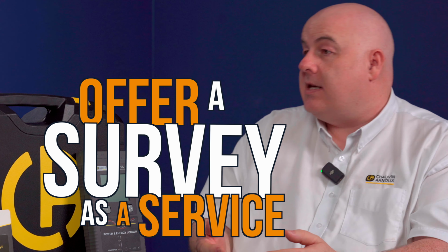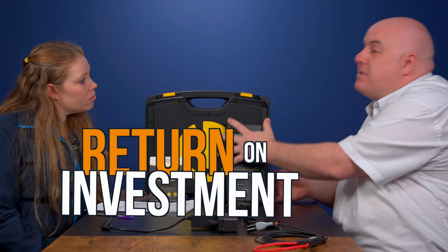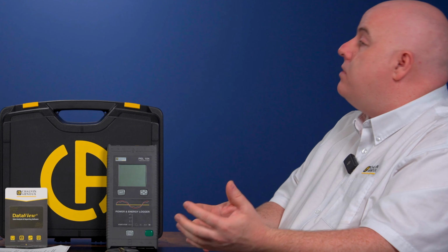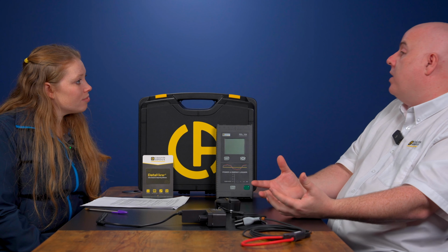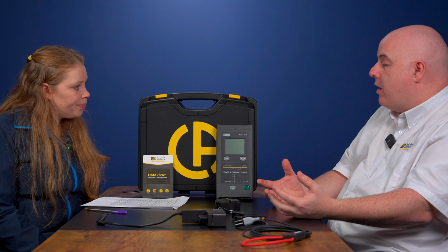But what we're seeing is a lot of our customers are starting to get into this. When they get a PEL 104, they can offer a survey as a service, so they can actually get a return on investment for having the PEL. We talked about, say, nuisance tripping. Other than saying to the customer, well, just phone me if it happens again, there's very little solution, whereas having something like a PEL 104, you can put it on, you can monitor the electrical installation over a period of time.